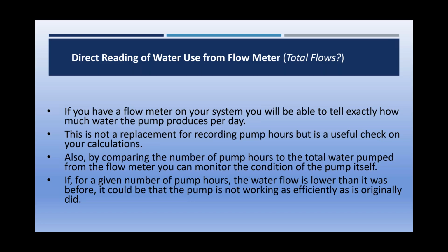And sometimes pumps actually wear out. Propellers, for example, on pumps can wear, and they'll then be producing less water. And it's important to know when that's happening ahead of time, so you can get a well installer to come and look at your system before your pump actually fails. Particularly if you happen to be unfortunate enough to be in a system that only has one well and one well pump in it.